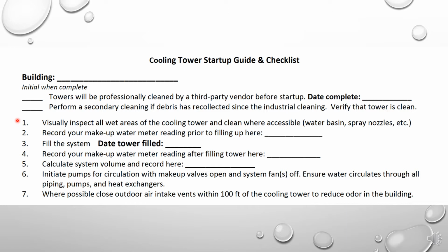You want to visually inspect all your areas, make sure everything looks good. We're asking you again to record your makeup meter prior to filling, and then fill it, and then record your makeup meter after you fill. This gives us a total system volume to make sure that we are consistently dosing these towers at the right amount. If you have any concerns about your makeup meter or how to access it, let myself or Peter Miller know. You want to calculate the system volume, so the difference between number 2 and number 4.